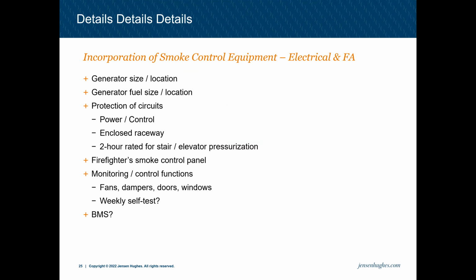However, ensuring that the generator is sufficiently sized to supply and power the fans and equipment for smoke control, looking at the generator fuel size, and then location, because generator fuel tanks can be a big impact on a building based on possibly secondary containment necessary or fire rated protections of those fuel tanks.